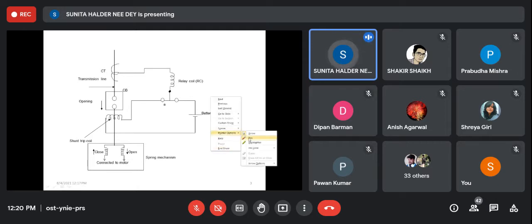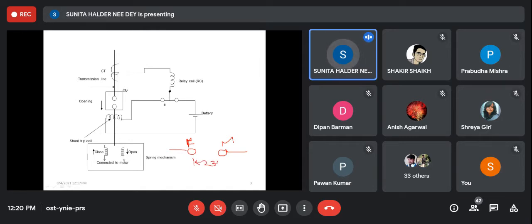You know, when we open the circuit, say this is the fixed contact, and there is the moving contact, I am writing M. Then what will be the voltage appearing across the circuit breaker? The system voltage. So if the system voltage is 230 kV, then this 230 kV will be available across these circuit breaker contacts. So the gap between the fixed contact and moving contact should not be very low. Otherwise, what will happen? There will be ionization of the intervening medium between them, and then the circuit will continue to conduct.